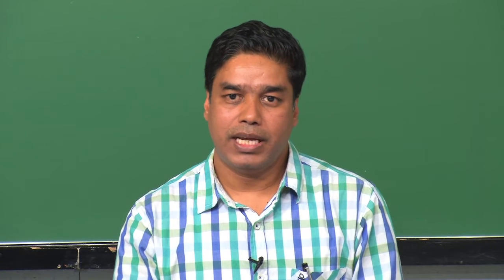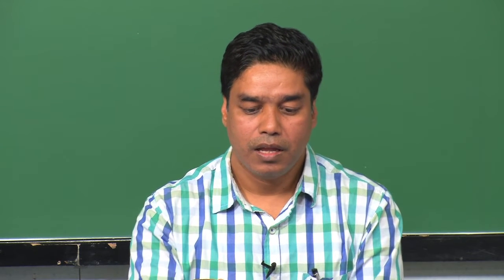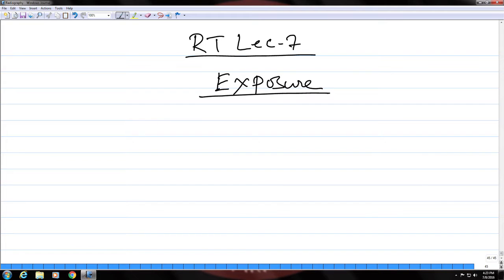Now, when you take a sample and do this exposure for capturing the X-ray image, what you control on the control unit is primarily the exposure time for a given tube voltage and given tube current. This tube voltage and tube current, on the other hand, can also be varied for a given exposure time. So, first you need to decide what should be the exposure time for a given tube voltage and a given tube current.